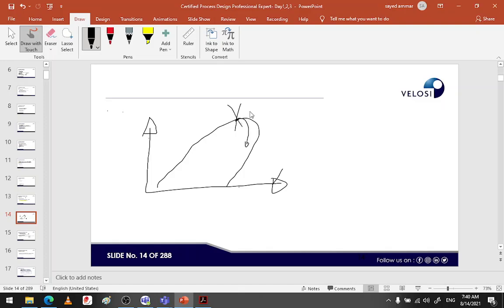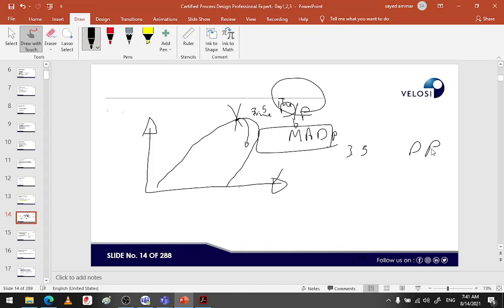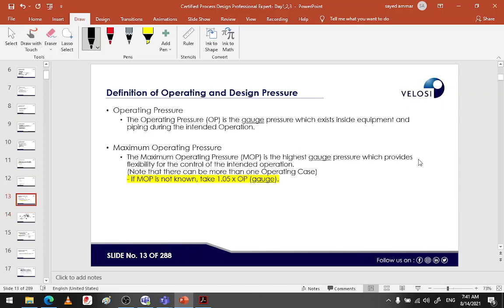Here at this point is almost 3.5 times the design pressure. What's the meaning of the design pressure at this time? It is not the design pressure we are saying on our P&ID. Here what we are referring to is the maximum allowable design pressure, which is equal to 3.5 times our design pressure. I don't get it. Why are you saying a lot of things like this? Why are we saying this now? Because at this stage, on this slide, we need to define the maximum operating pressure from the operating pressure.